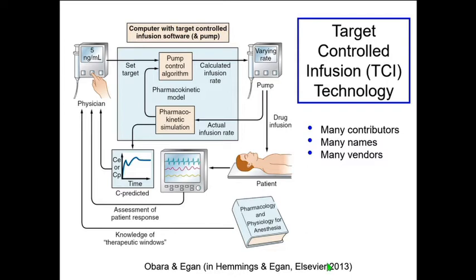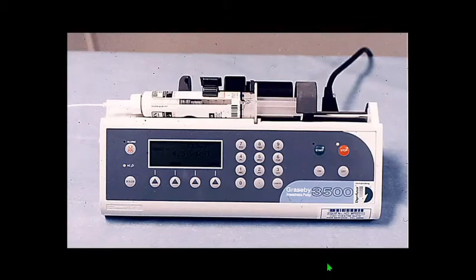As an example, if you were doing burst suppression for a neurological case and had 8 mics per mil of propofol going to create burst suppression, and when it's no longer necessary you say, okay, now I want to go back to 3 mics per mil for a usual anesthetic state and push go, the pump might be off for half an hour. That would be unusual for Americans to tolerate, but the pump is very courageous, so it will do it. This is a picture of the first TCI system.